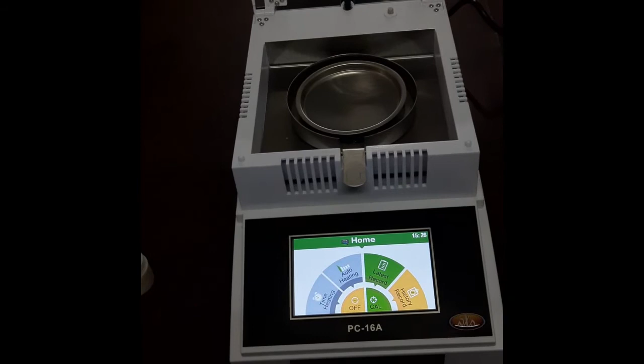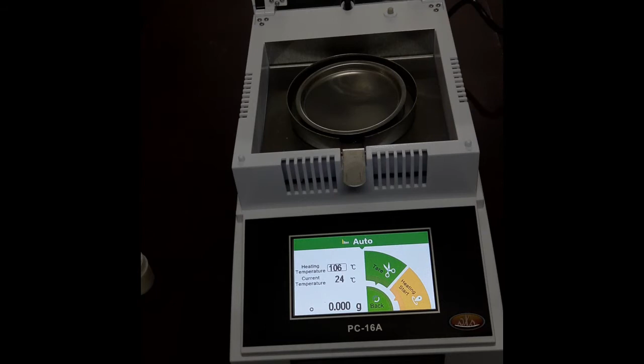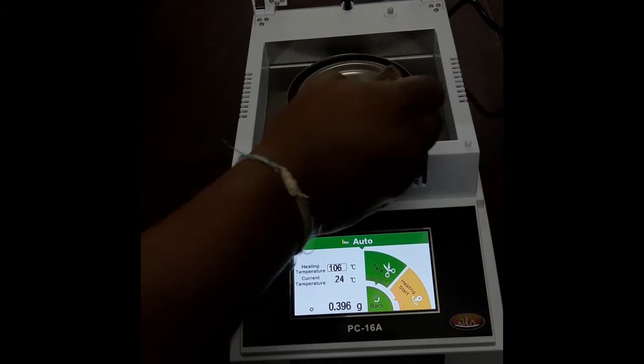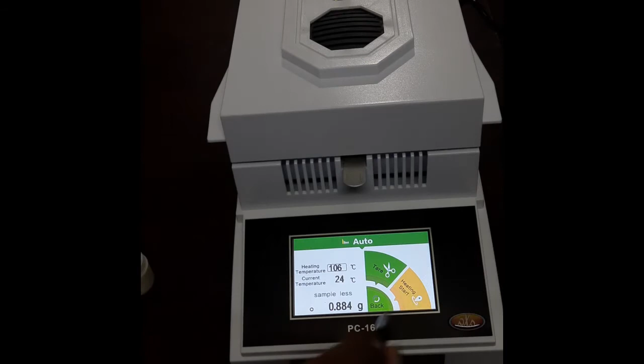This is the halogen lamp, and this is the temperature sensor. To run a sample, I am choosing the auto heating option. Minimum 1 gram sample we need to take. If you take less sample, it will show here sample less. So suppose I take 0.8 grams, if I press heating start, it will show you sample less. So minimum 1 gram we need to load.